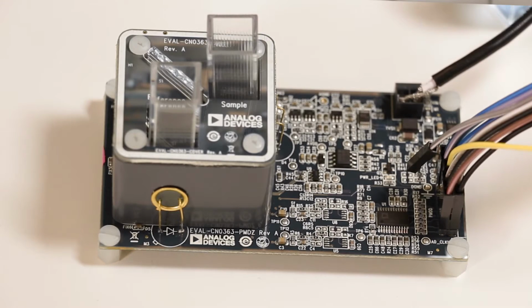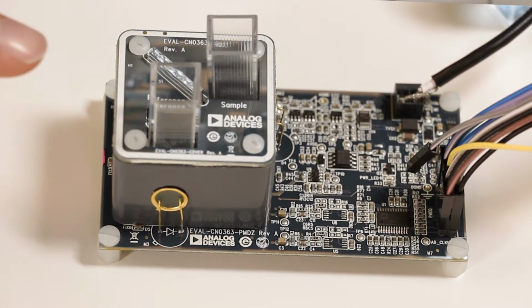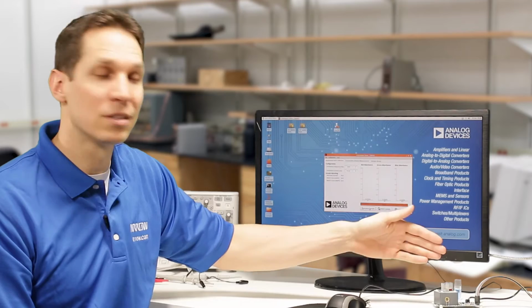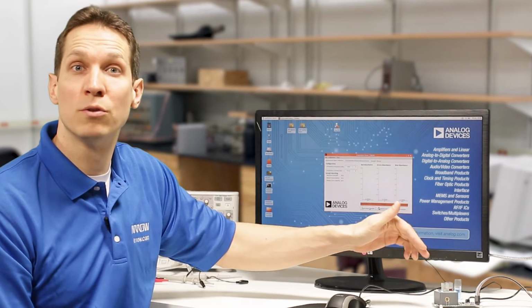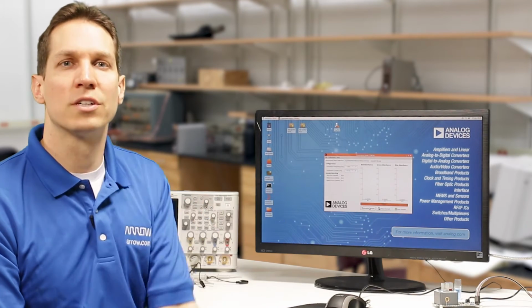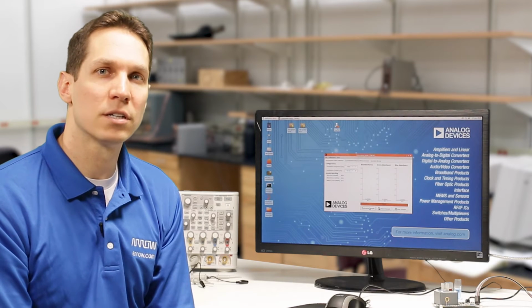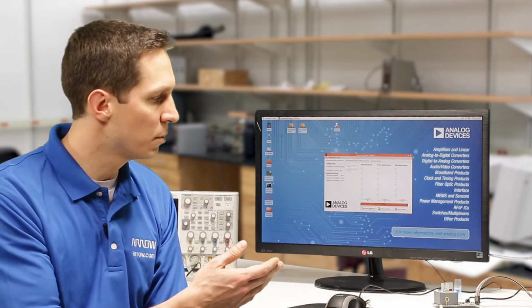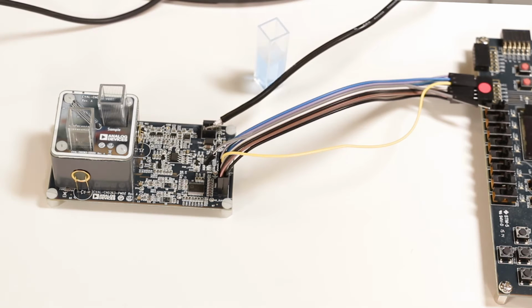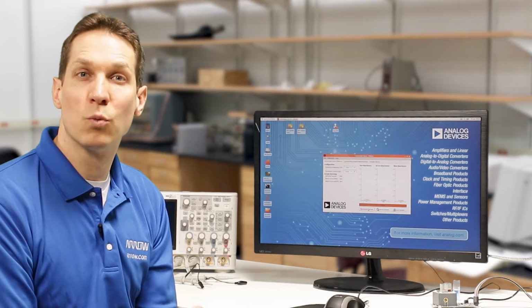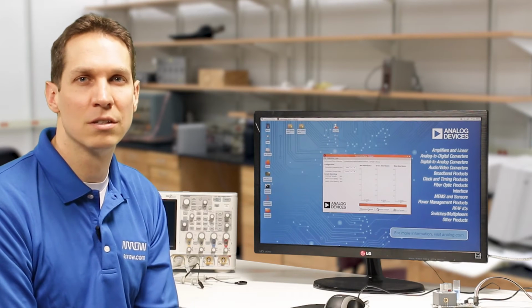Back to the light sources, the modulated light travels through a beam splitter seen right here, sending half of the light through the sample solution and the other through a known reference solution. Photodiodes are used to detect the light level, and the output current is converted to a voltage by a transimpedance amplifier. A transimpedance amplifier is an op-amp configuration that converts current into a voltage and is one part of the design where drift is a concern.